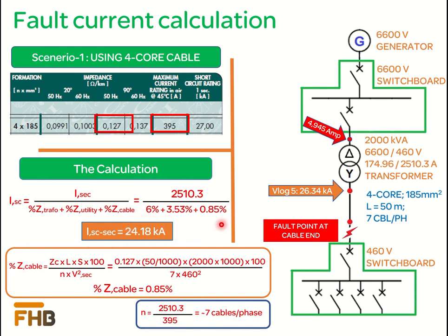It is important to note that in our last video the value of short circuit current at transformer secondary terminal without taking the cable effect was 26.34 kilo amperes. Therefore we can say that the cable helped in reducing the value of short circuit current to 24.18 kilo amperes.